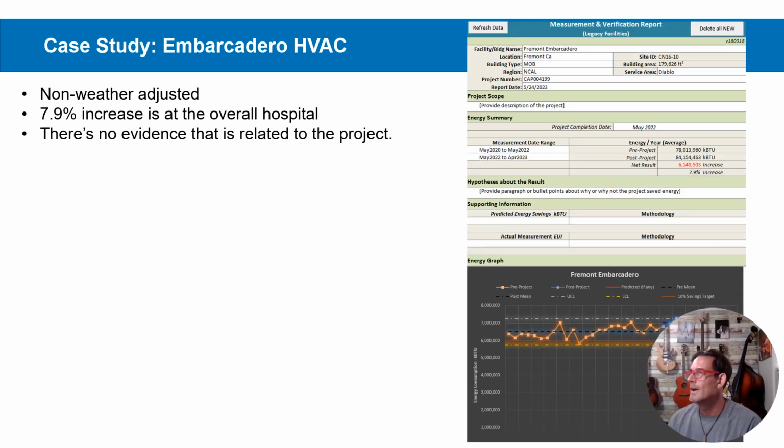And of course, the final energy on this, we did see a 7.9% increase at the hospital, but honestly, there's no evidence that that's related to the project at all. The project had to do with this 10% portion at the MOB. We're seeing some changes on the meters, but there's no way that we can say that that's related.